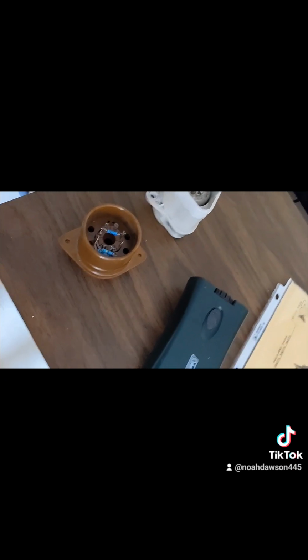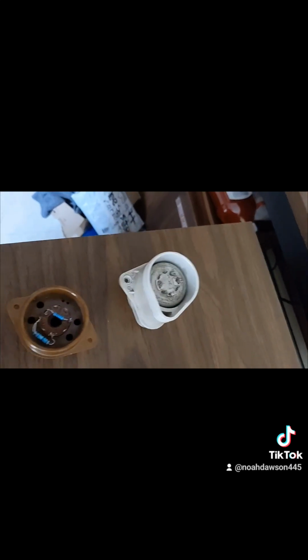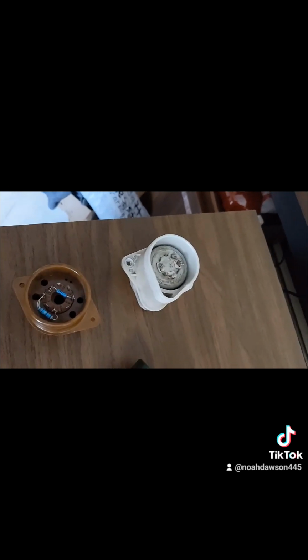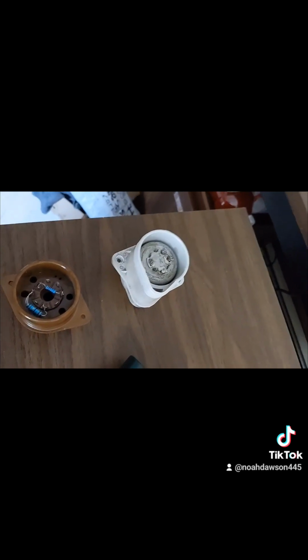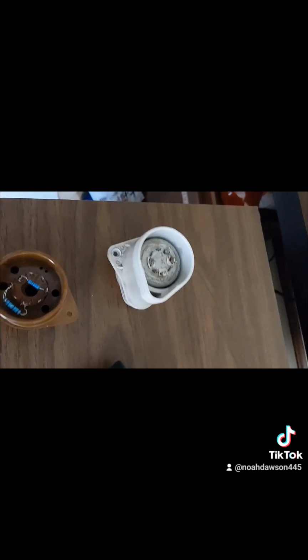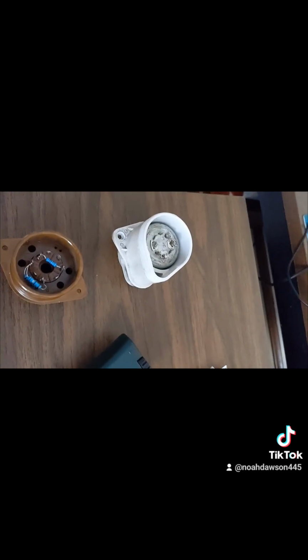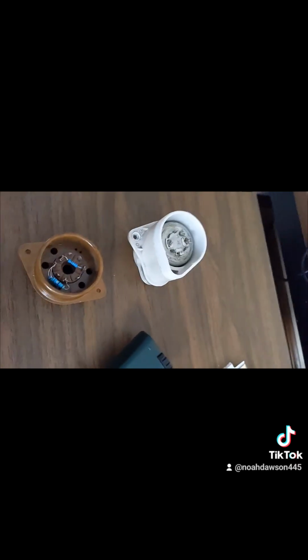From what I saw, the arcing went from the top of the cup up into that area, but there was a second arc at the bottom of the high voltage cage. It looked like there was a pinhole punched through where the wires wrapped around the stick at the bottom of the winding, underneath the flyback transformer donut. There was so much voltage it punched a pinhole through it, and it doesn't take much. When that dielectric insulation breaks down, it will jump to whatever it can to reach ground.